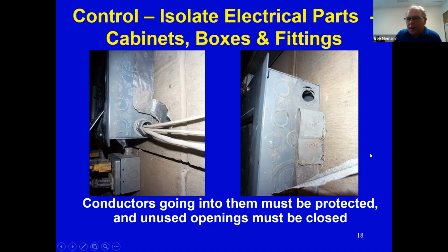If you're going to take a cover off of a box or panel, always look at the sides. Make sure that there's nothing as far as the knockouts that have been opened up on there. And it's such a hazard to me anyway. People look at that and say, well, maybe somebody could reach in there, get their finger in there and get a shock or something like that, which is true.